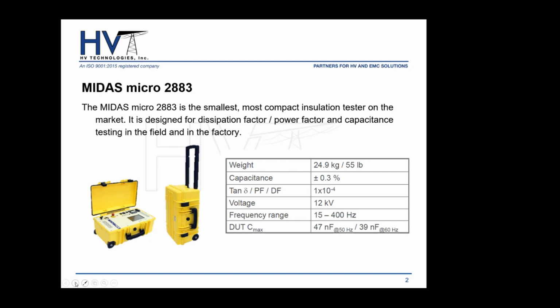And just to get into some of the basic specs, as you can see on the slide, it's the instrument itself, which you see here on the left-hand side. It comes in at 55 pounds, ultra light for this type of equipment. It comes with the wheels and a pull-out handle, so it's easy to transport, move around. Very important is the high accuracy of this instrument. Also, we have plus or minus 0.3% on your capacitance measurements, and 1 times 10 to the negative 4 on your dissipation or power factor or tan delta measurements. This is very important since the tan delta measurements are usually very small, so it's good to have high accuracy in order to read these very small measurements.